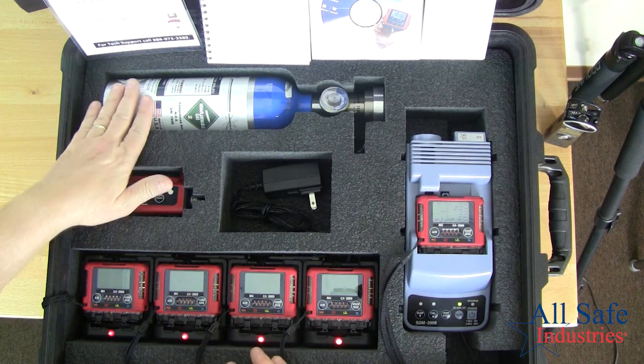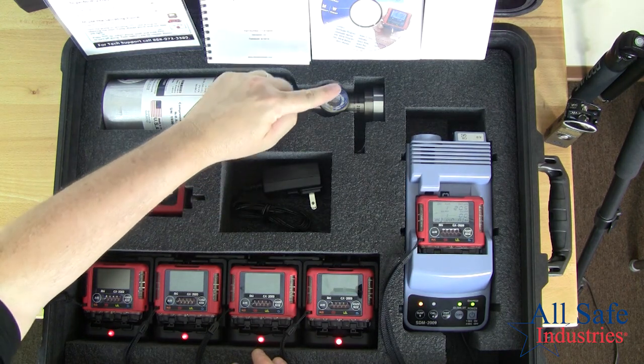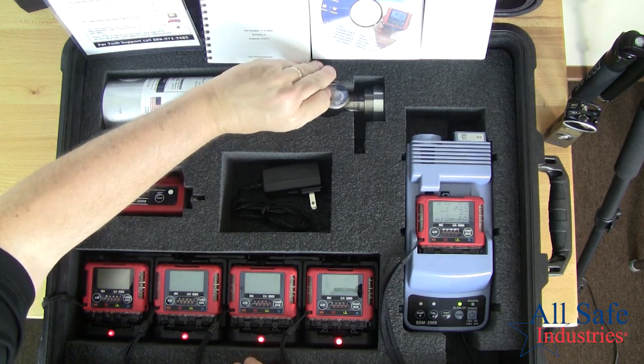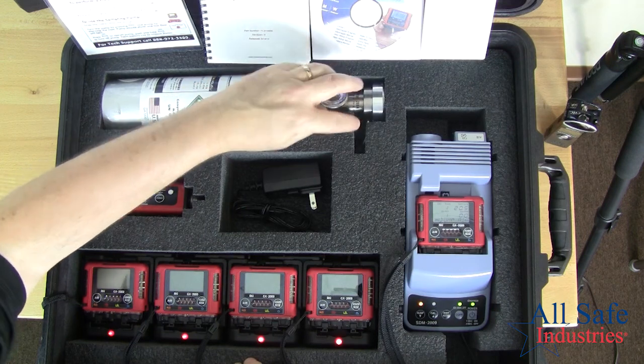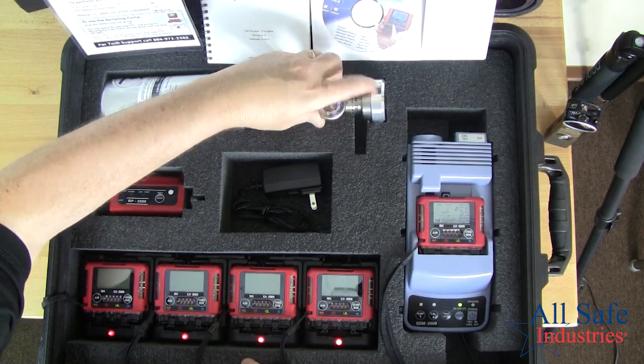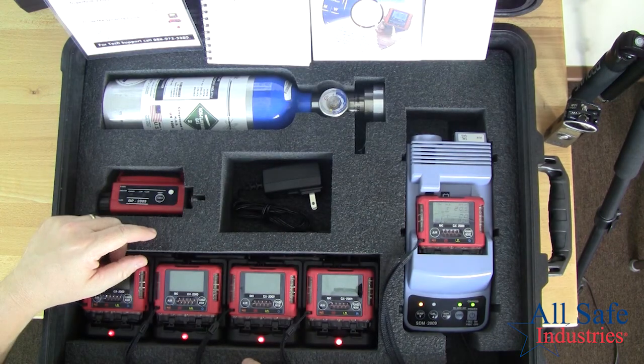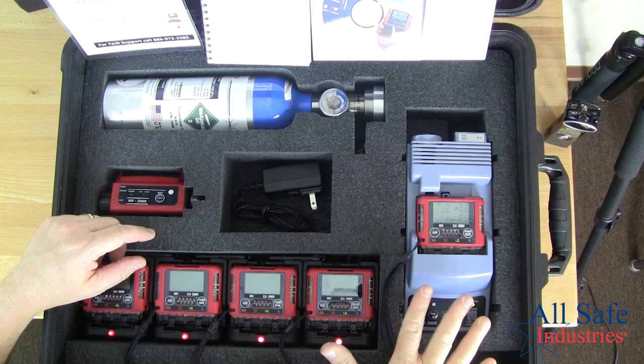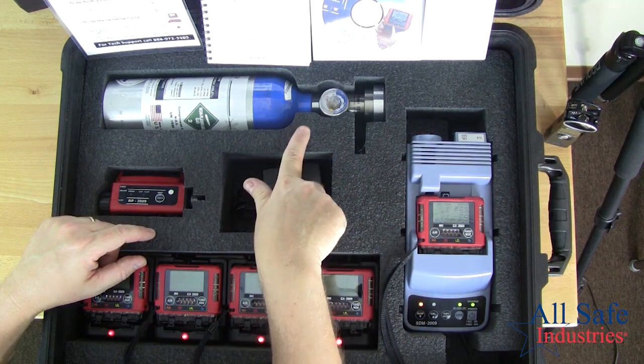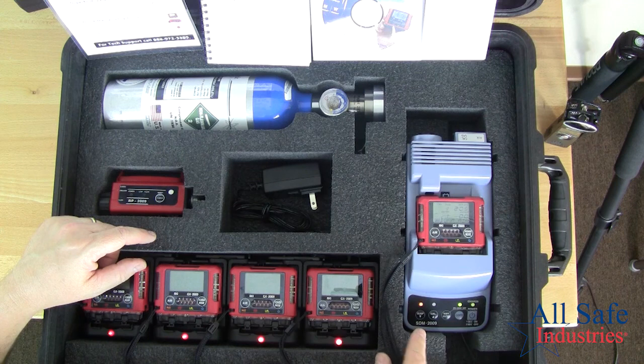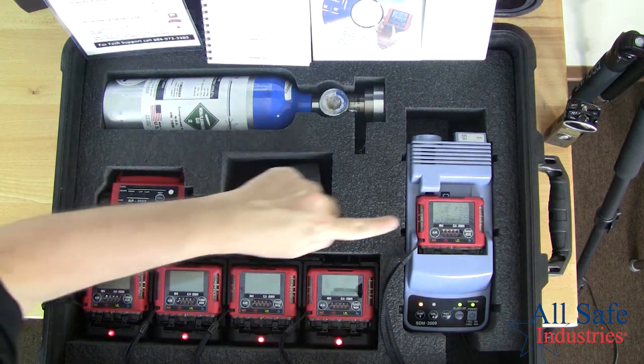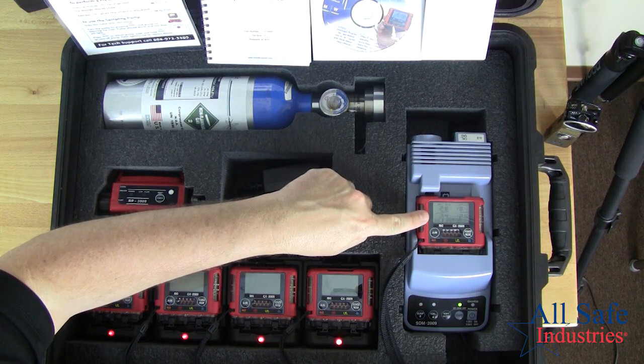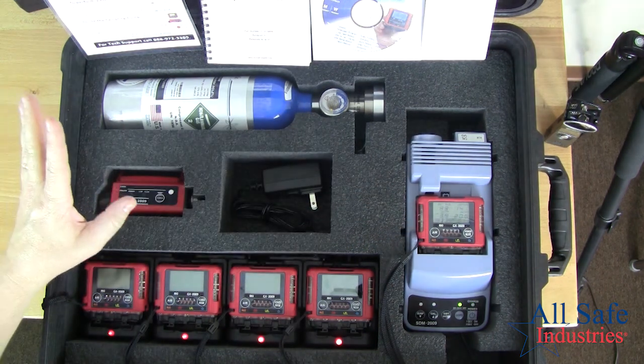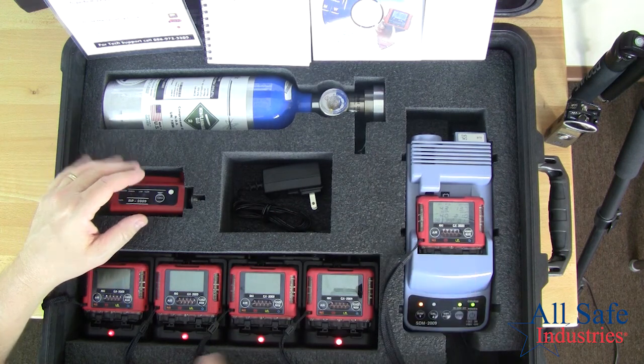So what we've done is your calibration gas is set up on a demand flow regulator. The demand flow regulator allows gas to flow automatically when the cal station calls for it. And so first it will purge the instrument with fresh air, and then you'll hear a click, and that means it's going to start sampling gas to the meter so we can do a bump check. So there went the click, and now it's going to start doing a bump check on the sensors in this unit. It's a fairly quick process and it's automatic. I don't have to do anything.